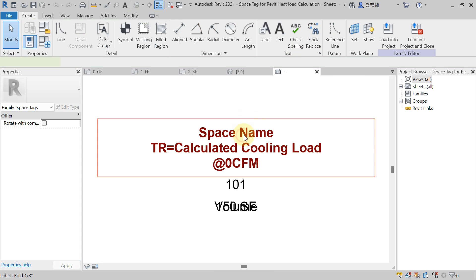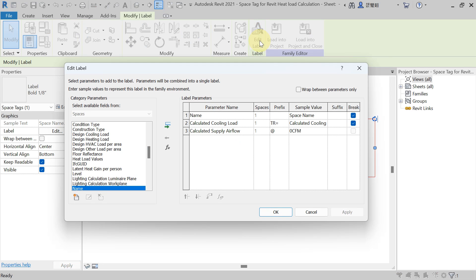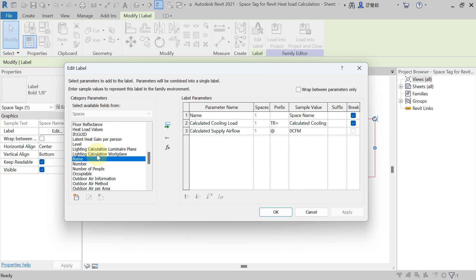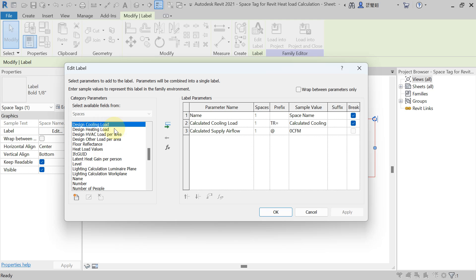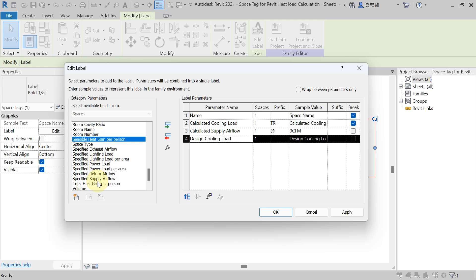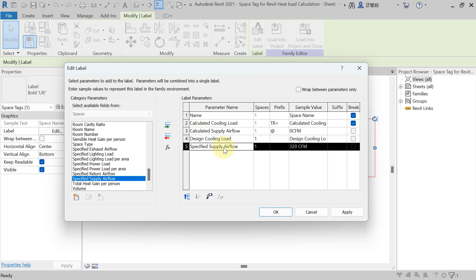Select the label and click Edit Label. Here you can see Calculated Cooling Load and Calculated Supply Air Flow — these are from the heat load calculations done in Revit. To see the updated cooling load and specified air flow after the changes, add Design Cooling Load and also add Specified Supply Air Flow. Write zero for the decimal places.